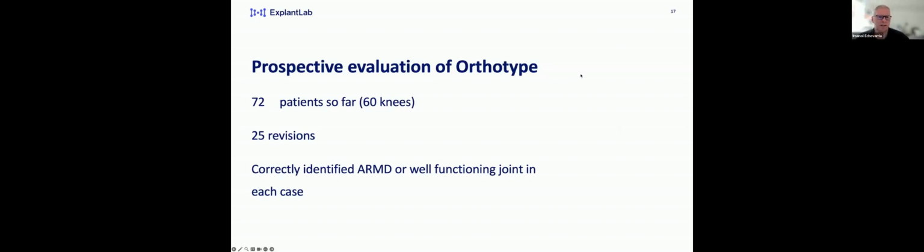So we have been working in the UK just to get post-marketing evaluation of the product, to be able to demonstrate to customers the applicability and the accuracy of this. We've had 72 patients so far, 60 in knees, 25 of these revisions. In each of these cases, it correctly identified whether there was ARMD or a well-functioning joint. That was compared with histology, so we could tell by histology whether there was an active ARMD taking place. So we're pretty happy that the post-marketing analysis is demonstrating what we saw in development.